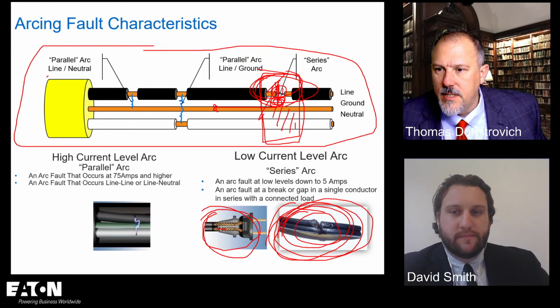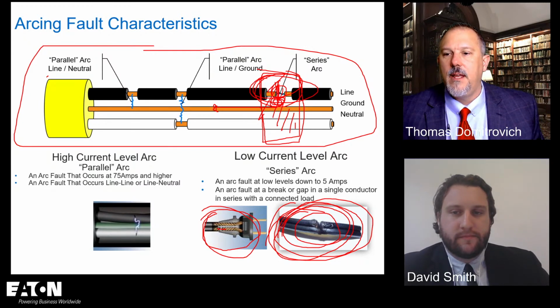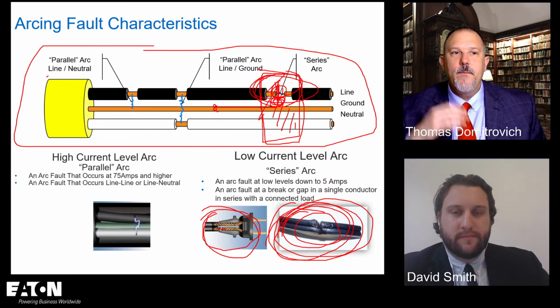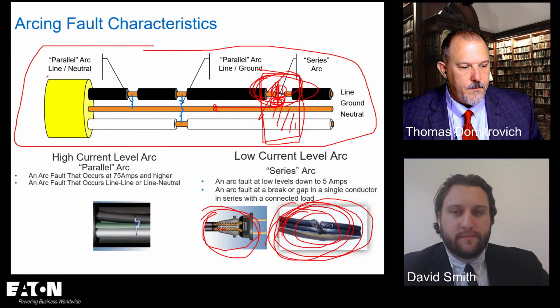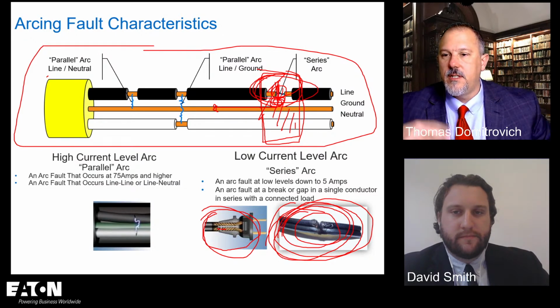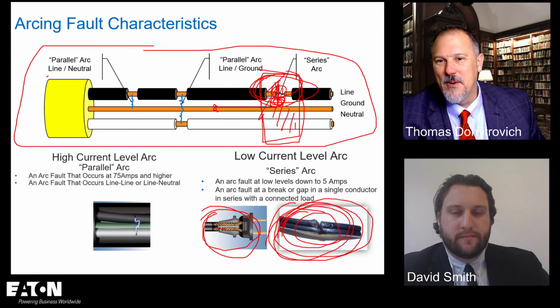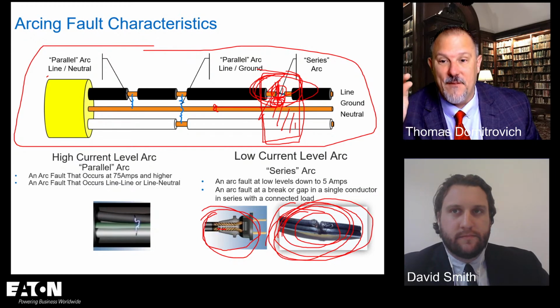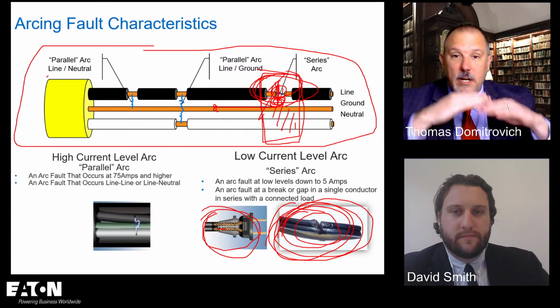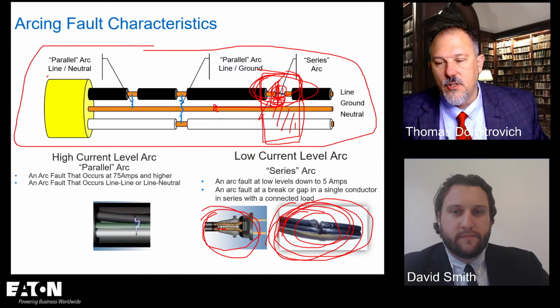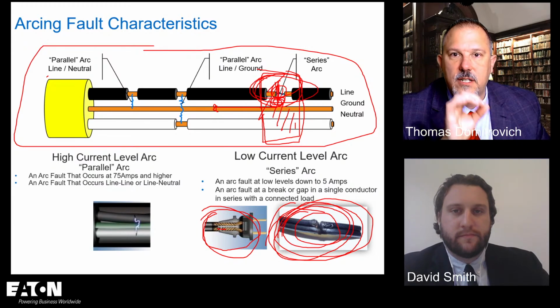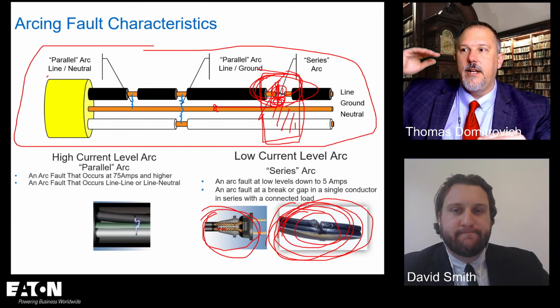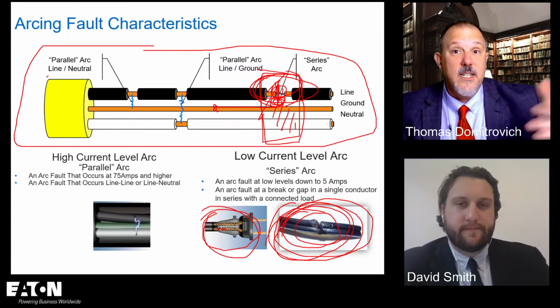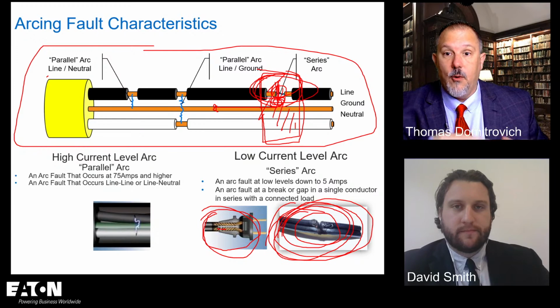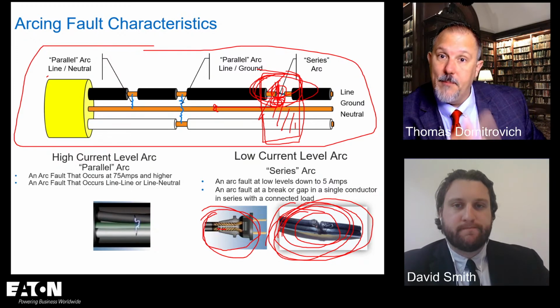Do signals or frequency sent over the conductors affect the AFCI? Robert, here's the thing. I would say it's the signals and frequency. I remember way back in the day when we were experimenting with combination type AFCIs, looking at that 5 amp series arc, we look at multiple frequencies, and most manufacturers will do this to detect that arc. They don't look at just the 60 hertz. We're looking at 60 hertz, we're looking at 120, whatever the numbers are, I don't even know. And some of it might even be patented, the algorithms for how we determine what is a good arc and what is a bad arc.